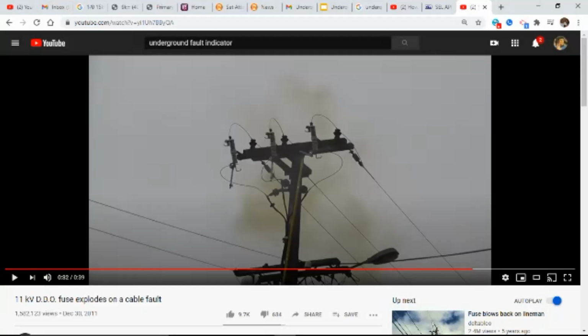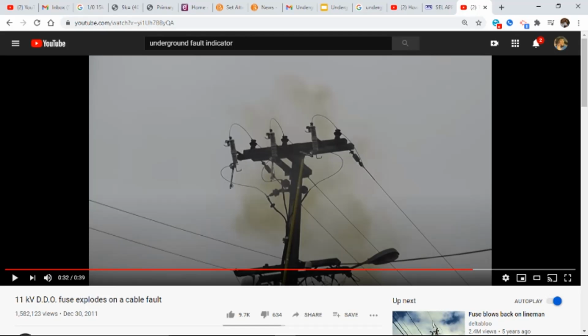A squirrel gets on a line and gets shocked and blows a fuse, it usually falls away. Or a tree limb causes a fault, or an animal. Typically when that happens on overhead, it kind of clears itself. That's what we call it. It clears itself. So all you have to do is, well, yeah, I found a squirrel by the pole. All you have to do is go back and replace a fuse.